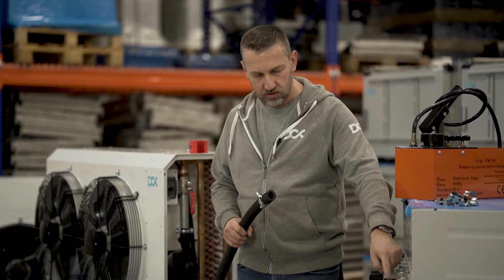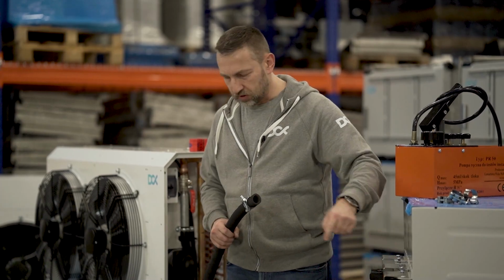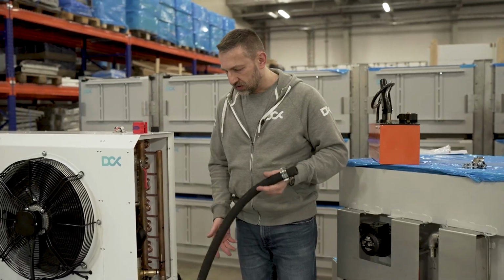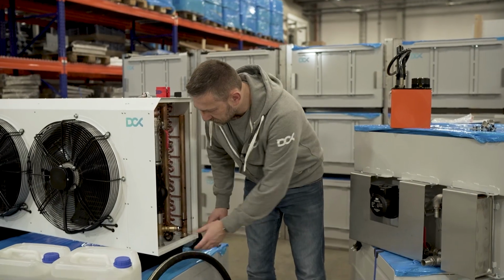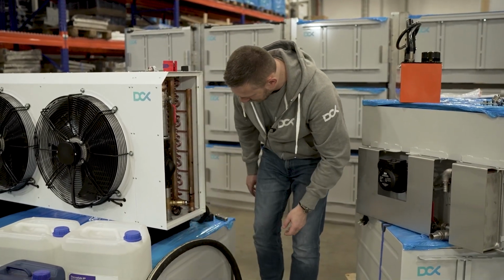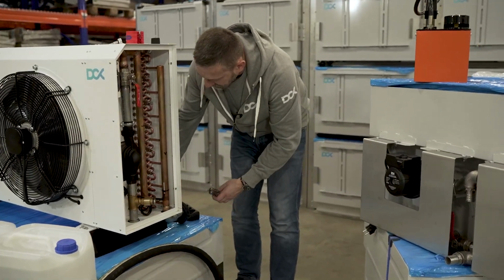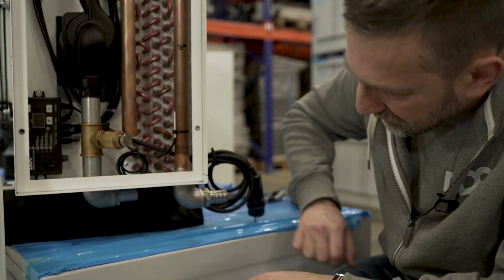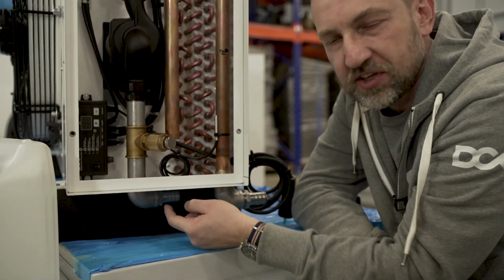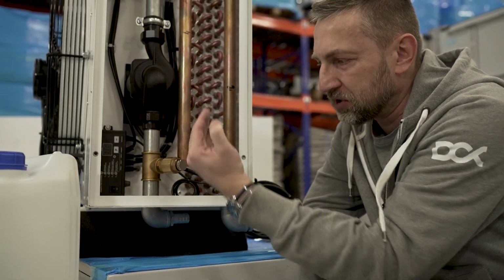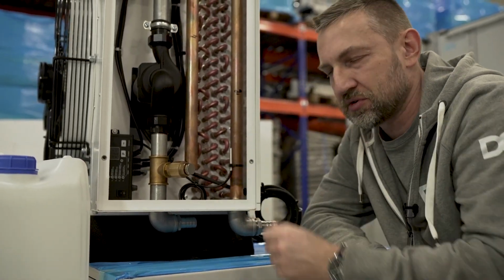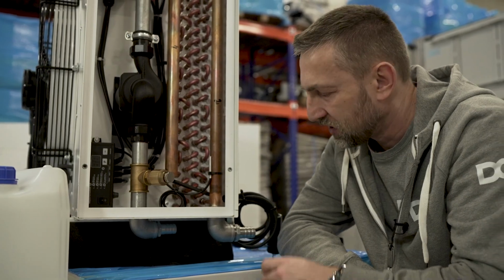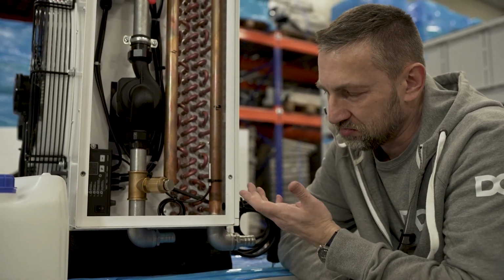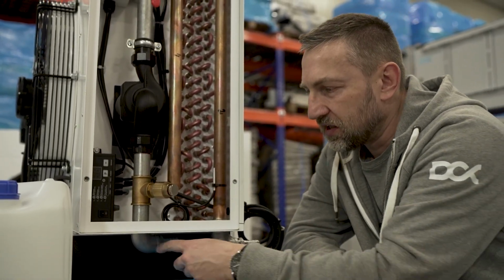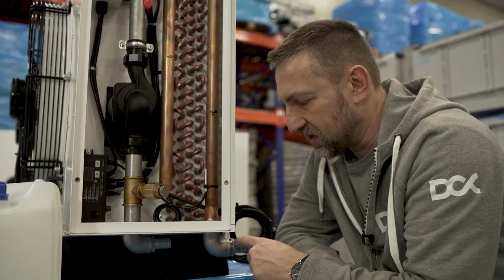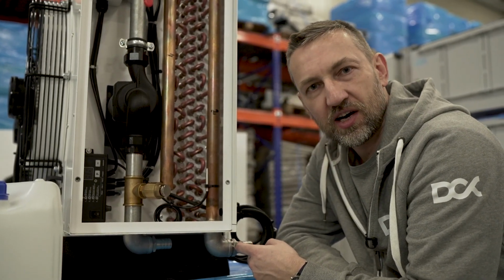What I'm going to do right now is I will connect the outlet tubing or outlet pipe to the inlet part of the dry cooler, and maybe I will first show you the important item, which are the inlets. As you can see, we have two fittings here. One is the inlet fitting, in the middle below the pump, that's the inlet. This is where the fluid goes to the dry cooler to be additionally cooled. That one is the outlet, right? So simple as that. The middle one is the inlet. The right one is the outlet.